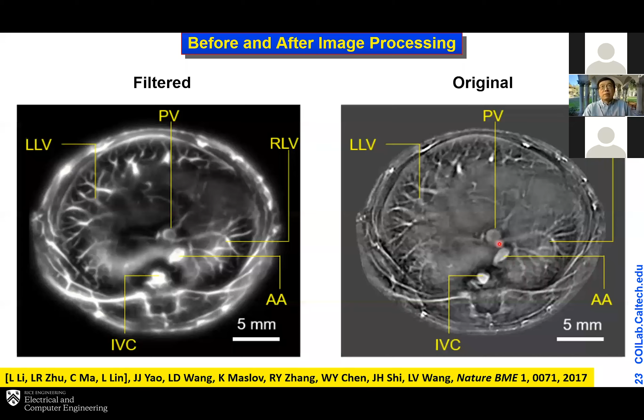The other aspect is the imaging frame rate. This is obviously very important. Rats have a much higher heartbeat, as we know, than humans, and they also breathe faster. So you've got to make sure your speed is high enough to take care of the motion artifact. At 50 hertz, you don't have to worry about any of those.